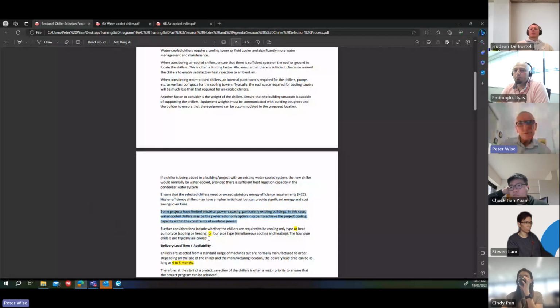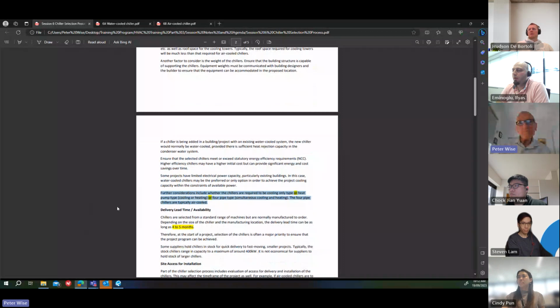They say, oh, we've only got 400 amps. What can we do? So you might find that a water-cooled chiller will do the job. And there'll be probably a higher cost for the job, but it will do the job. And further considerations include whether the chillers are required to be cooling only or heat pump type cooling or heating, which is now very popular, or 4-pipe type simultaneous cooling and heating. The 4-pipe chillers are typically air-cooled.